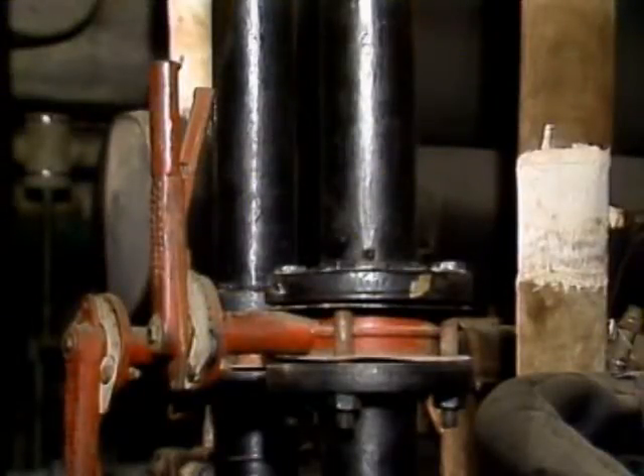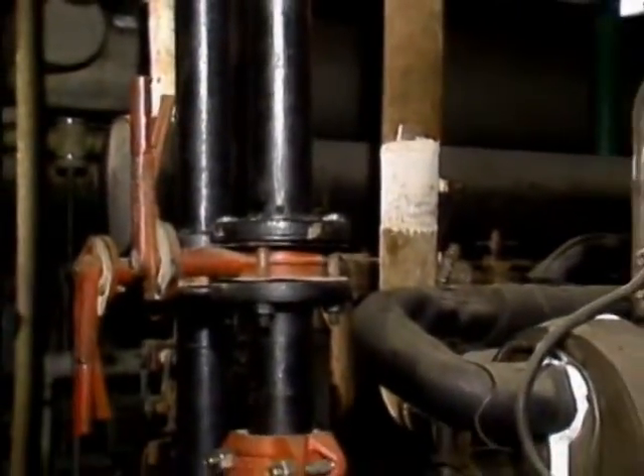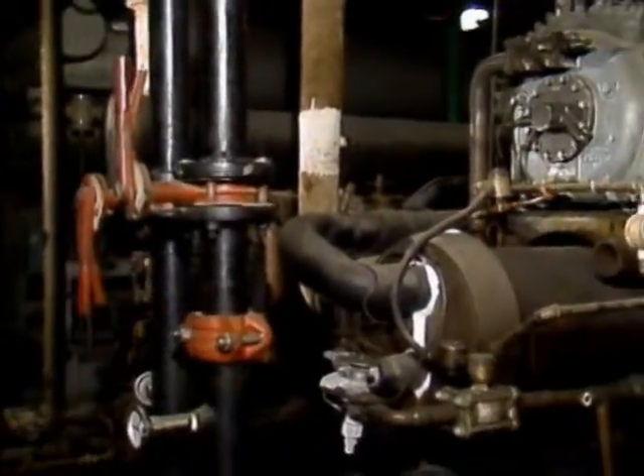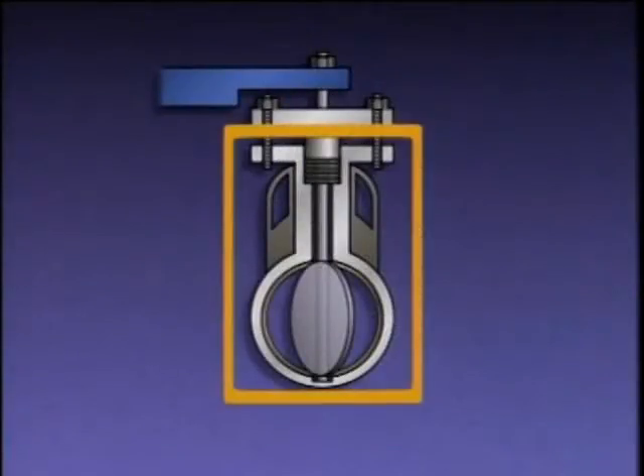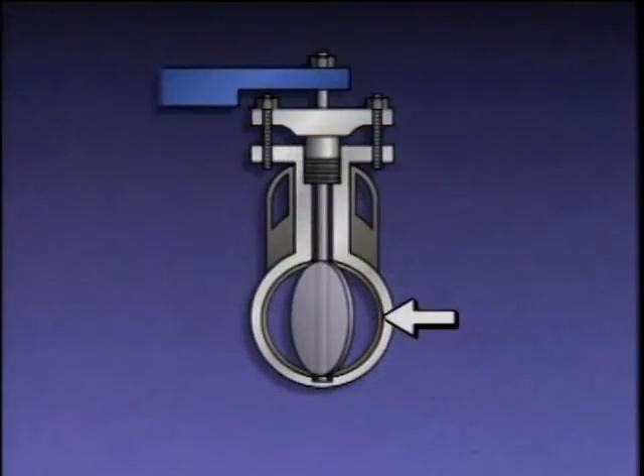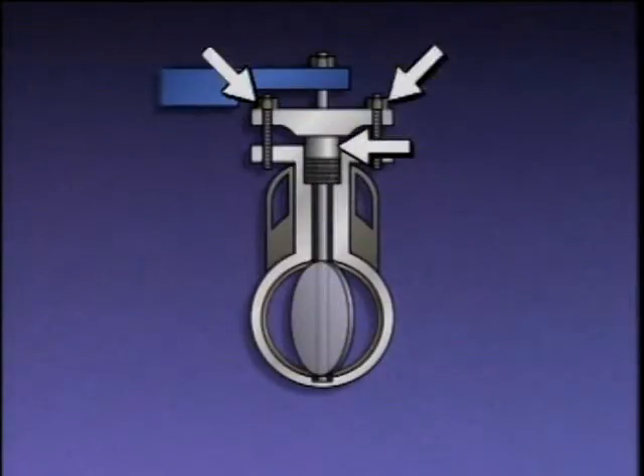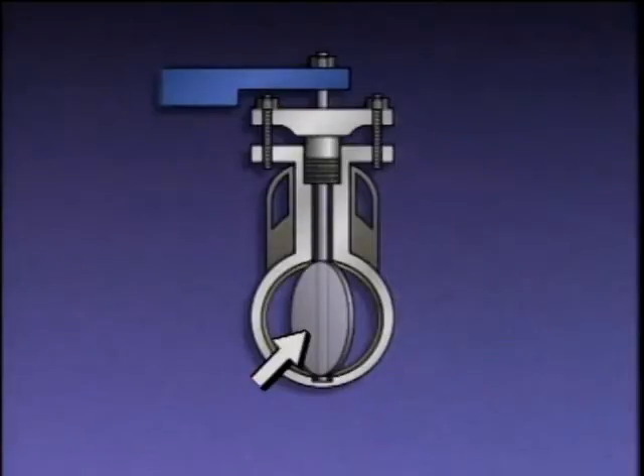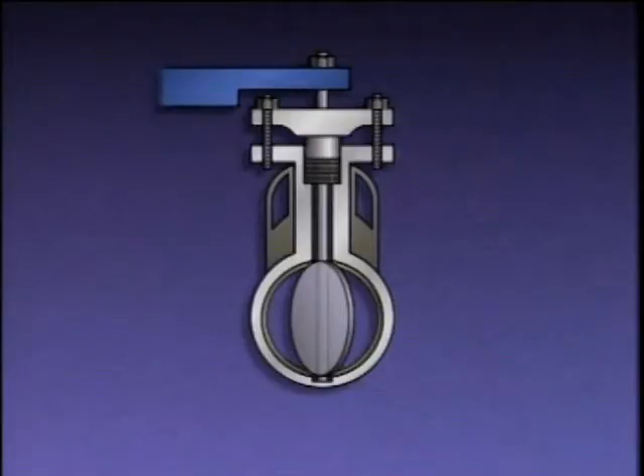Butterfly valves are used for a variety of purposes in industrial plants. They typically have round, relatively thin valve bodies, so they take up much less space in piping than many other valve types. A butterfly valve consists of a valve body, a seating area or seat, a disc, a stem with a handle, a stuffing box, packing, and a packing gland with gland nuts. The disc is slightly smaller in diameter than the inside of the piping and offers little obstruction to flow when the valve is fully open.